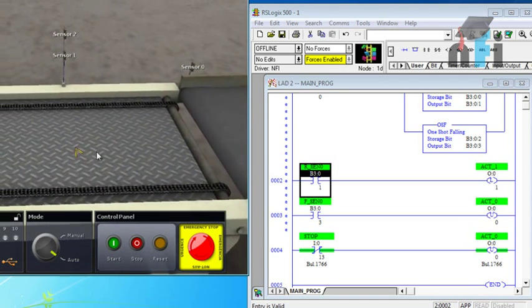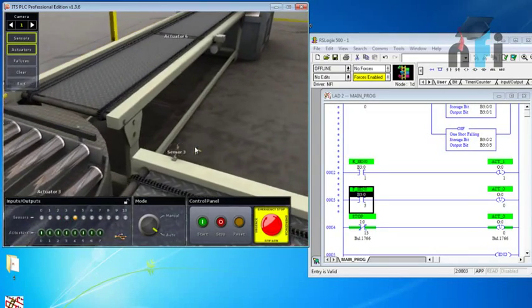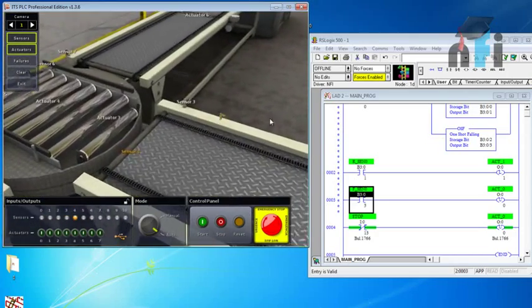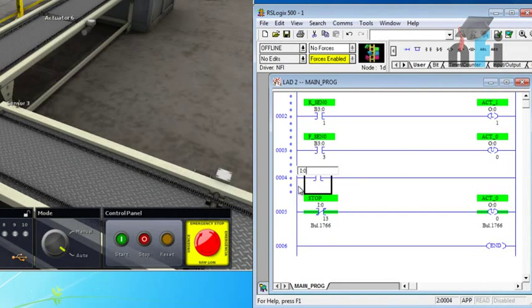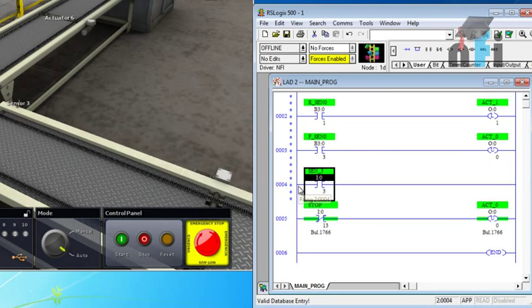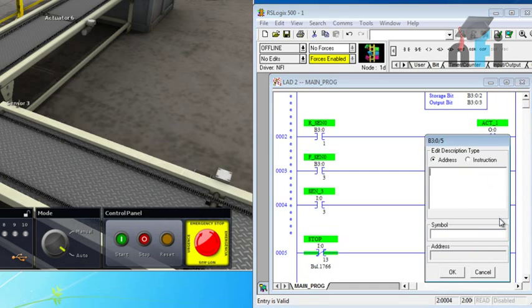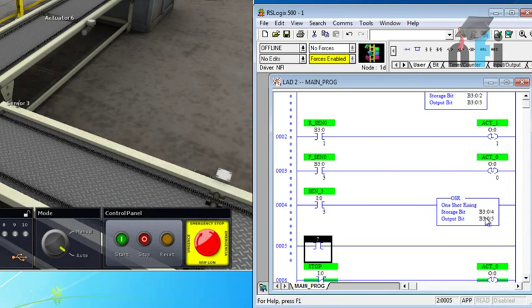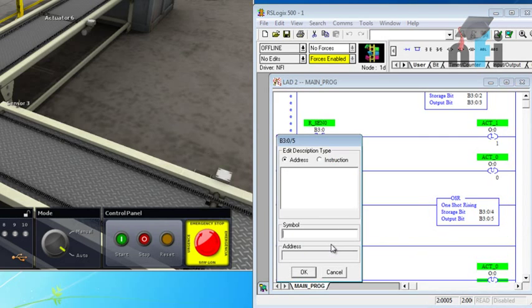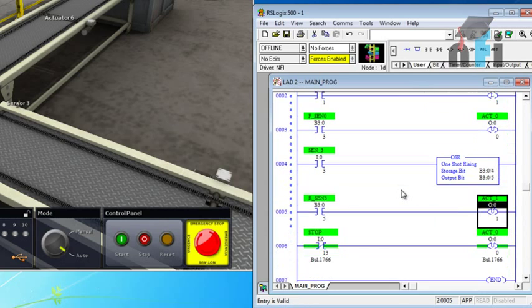Take another rung and contact, tag it with the output bit of the falling edge - falling sensor zero. Using this falling edge we unlatch actuator zero. So we have rising edge to latch actuator one, and falling edge to unlatch actuator zero. Now the box will travel forward to sensor three. Using sensor three we have to stop actuator one, so take another rung with I colon zero slash three - sensor three - and take one shot rising with B3 colon 0 slash 4 and B3 colon 0 slash 5.